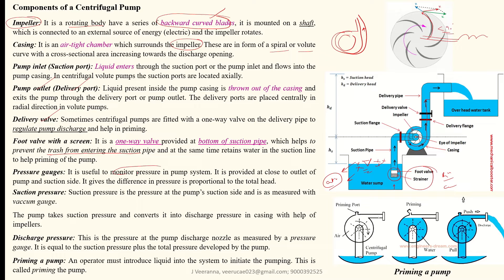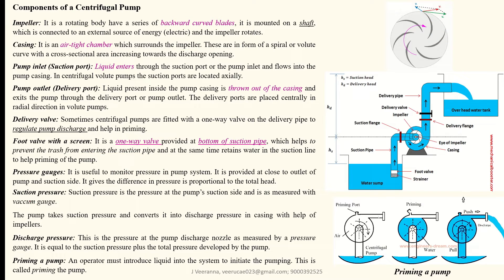The pressure gauge is used to monitor and check the pressure in the centrifugal pump — it provides readings at the inlet section and outlet or delivery head. The suction pressure is measured using a vacuum gauge, because the pressure on the suction side is always less than atmospheric pressure. The discharge pressure is the pressure at the pump discharge nozzle or outlet — at the delivery pipe — and is measured by a pressure gauge.